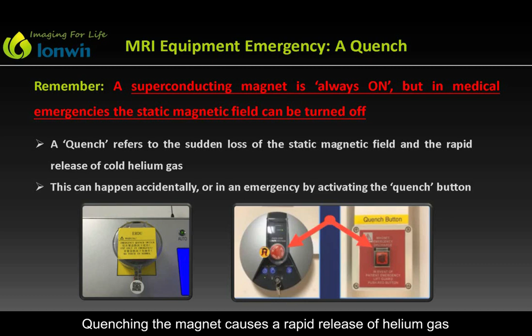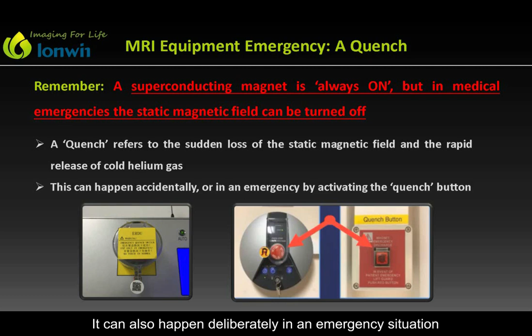As mentioned before, a superconducting magnet is always on, but an emergency situation may arise where the static magnetic field of the scanner needs to be turned off. This is referred to as a quench. Quenching the magnet causes a rapid release of helium gas, which results in a loss of the static magnetic field. A quench also can happen accidentally, for example, due to prolonged power failure. It can also happen deliberately in an emergency situation by activating the quench button.